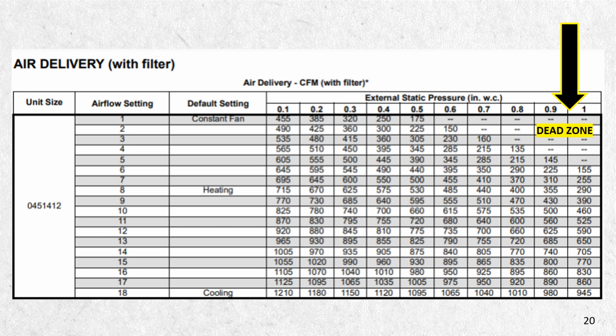This is probably one of the most important specs that you'll see on this one. We have a 1200 CFM furnace, putting out 45,000 BTU. Now this one comes factory set. When you look at this, this is your constant fan factory set to 1, factory set speed tap 8, and factory set speed tap 18. Now 1200 CFM. If you look right here at 0 resistance in cooling, I'm only going to get 1210. Now if you're pushing the limit on this and you need 1200 CFM for your cooling capacity, and let's say you do not check your static pressure. Let's say your static pressure is 0.9 to 1. Look at the CFM you're losing. Right here, that's what that puts out. If you're at a static pressure of 1.0, you're only putting out 945 CFM.